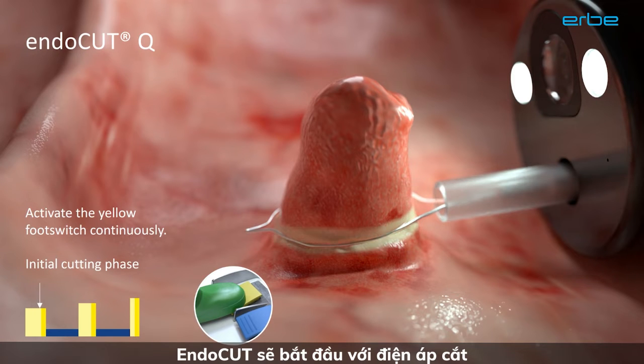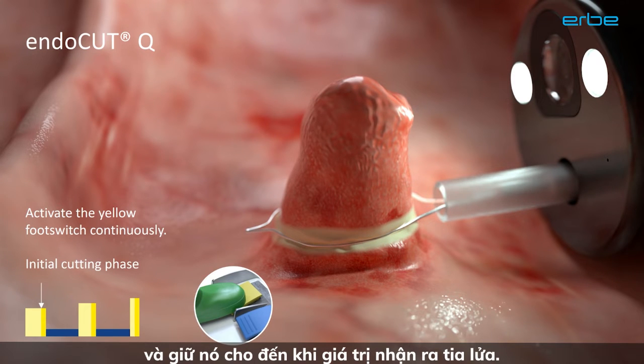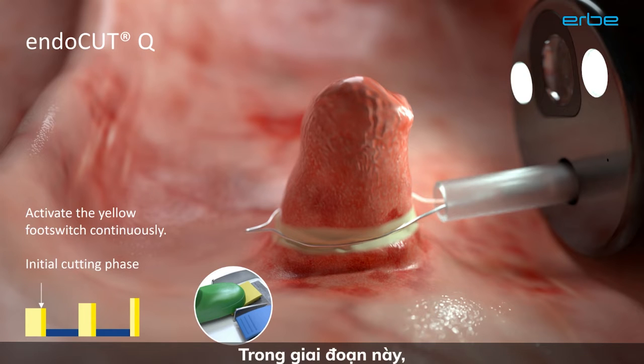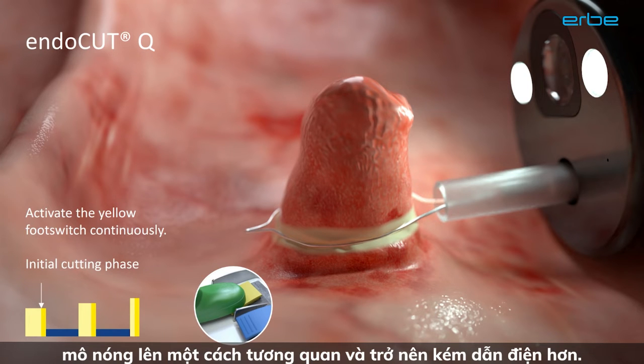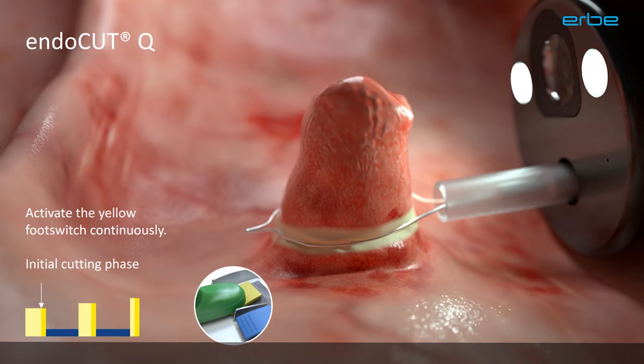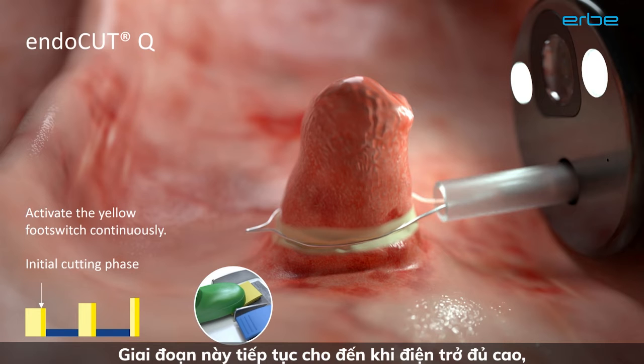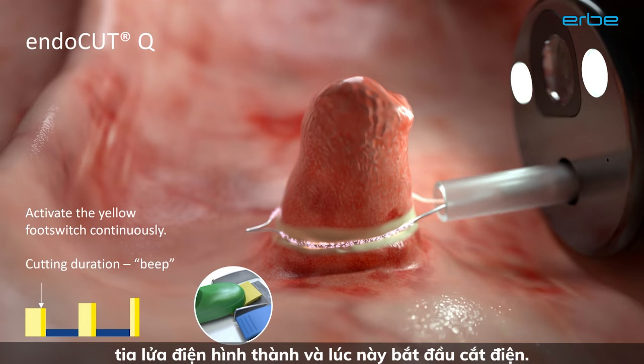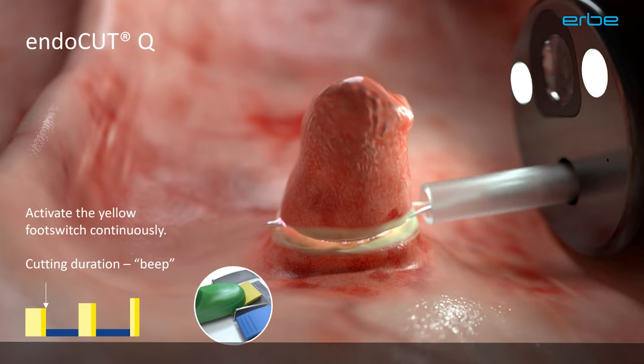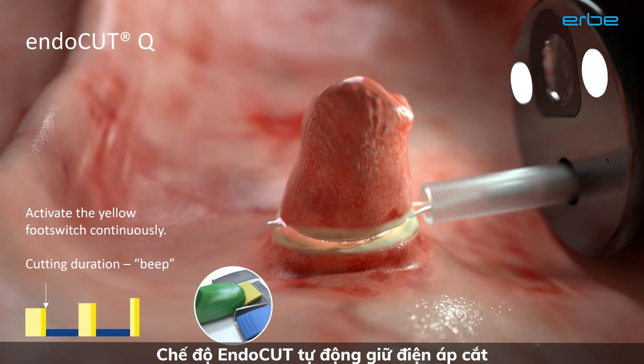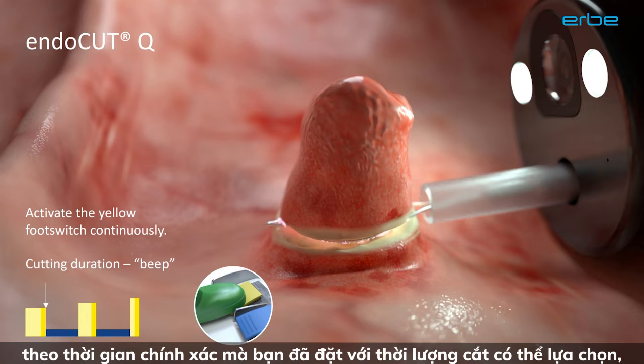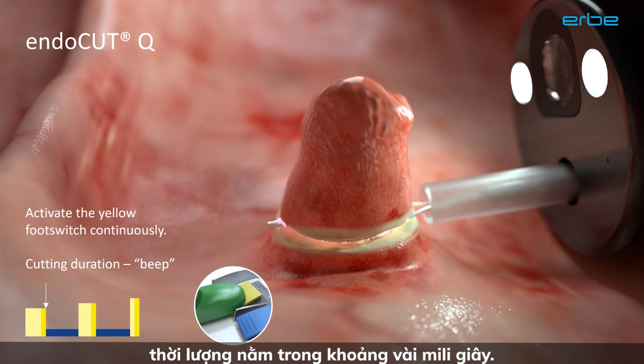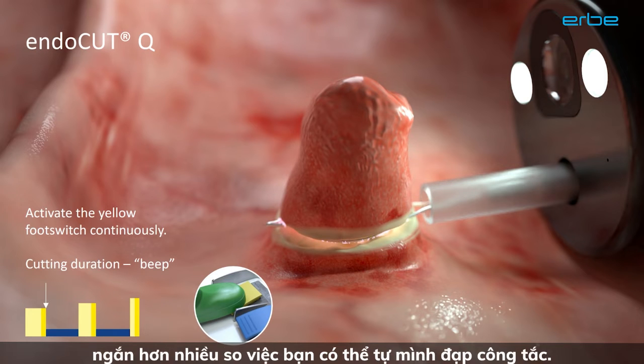The EndoCut will start with the cutting voltage and hold it until the Vio recognizes the spark. During this phase, the tissue heats up, coagulates, and becomes less conductive. We call this phase the initial cutting phase. This phase continues until the resistance is high enough, the sparks form, and now the electrical cutting begins. The EndoCut automatically holds the cutting voltage for the exact timing that you have set with the selectable cutting duration, which is in the range of a couple of milliseconds. So that is really very, very short. Much shorter than you could ever step off the foot switch by yourself.